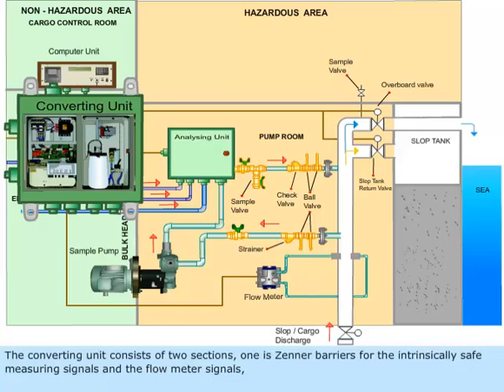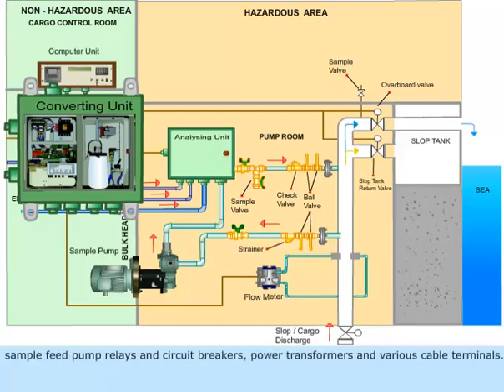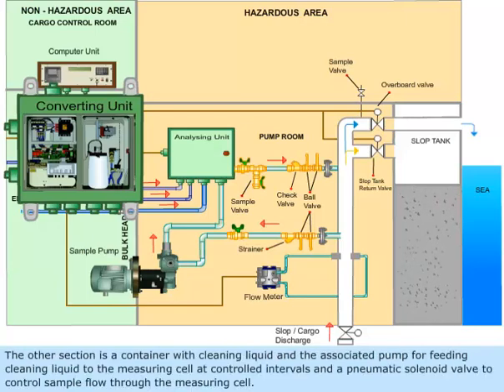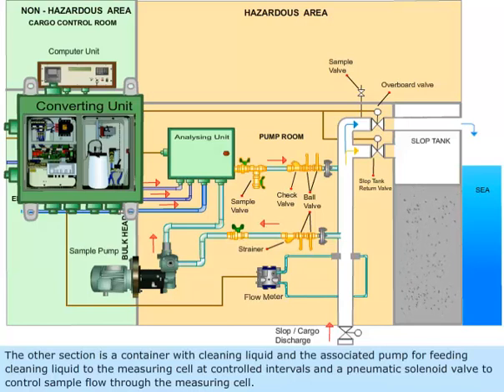The converting unit consists of two sections. One is Zener Barriers for the intrinsically safe measuring signals and the flow meter signals, sample feed pump relays and circuit breakers, power transformers and various cable terminals. The other section is a container with cleaning liquid and the associated pump for feeding cleaning liquid to the measuring cell at controlled intervals, and a pneumatic solenoid valve to control sample flow through the measuring cell.